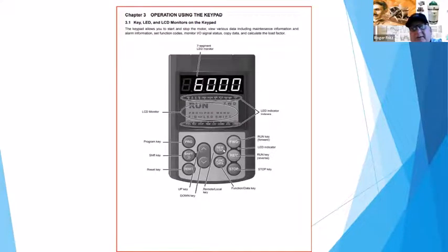Local remote, meaning is it going from the local connections on the board, or is it functioning from the remote connections? And then the function and data key allows you to adjust different things inside the program button. Then this is just start, stop, forward start, reverse start and stop. They're just digital contact inputs that allow that, but those also can be programmed in and out of the circuit, whether you need them or not.